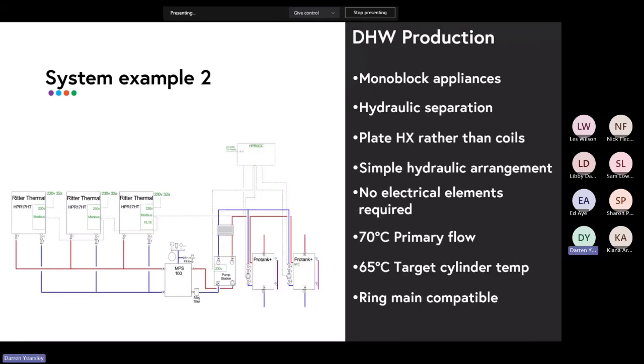We have another one which is similar. So this is a hot water system where we've got 60 kilowatts of recovery, and I believe it was 2,000 litres of storage. And you can see hydraulically how similar it is. So the air to water heat pumps connect onto the buffer, and then we pump out of the buffer. We've just got a single pump station on the system, and you can see where the plate heat exchanger is leaving the pump station. So that's the break between the mechanical and the potable water.